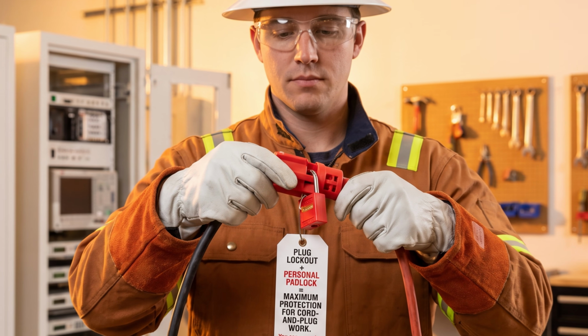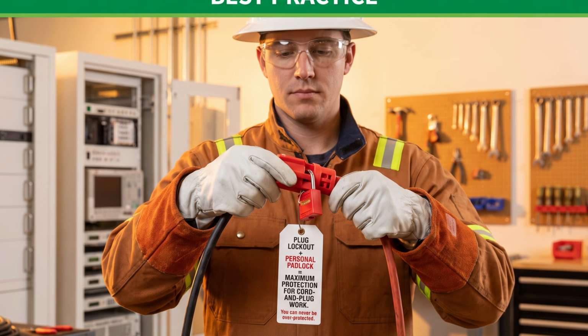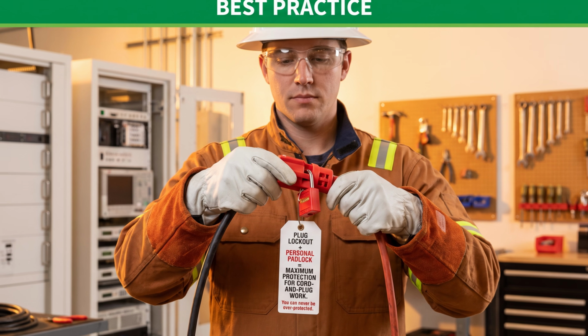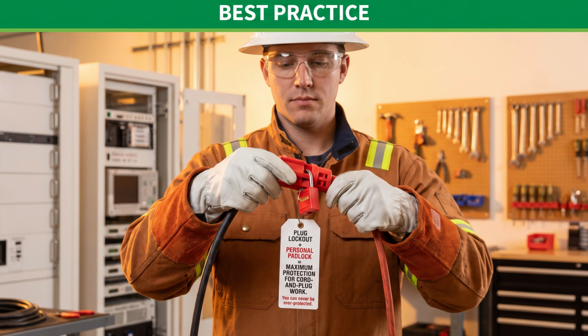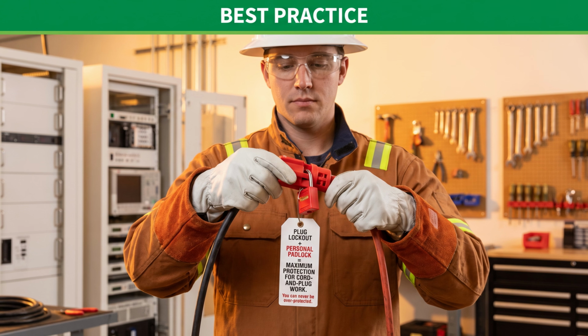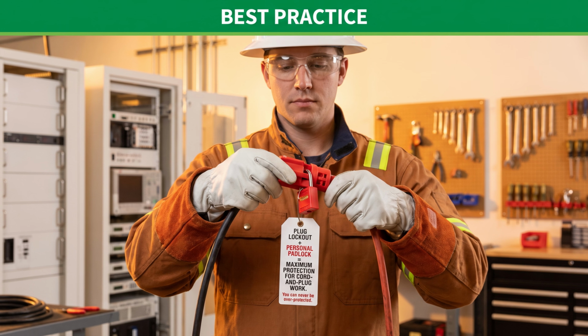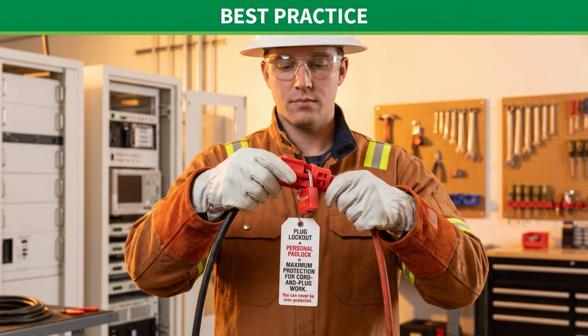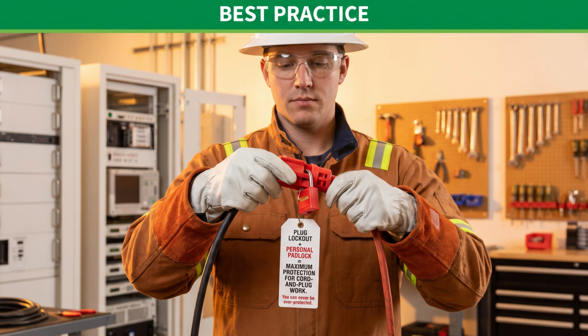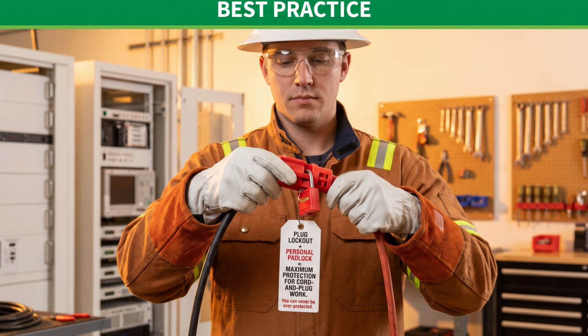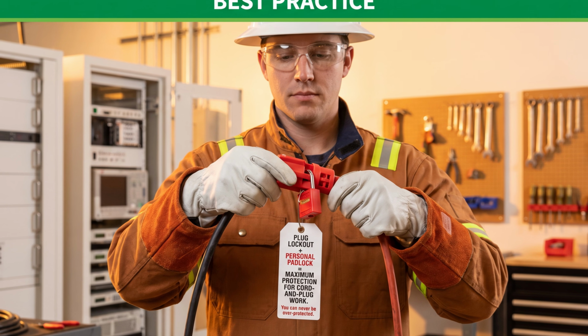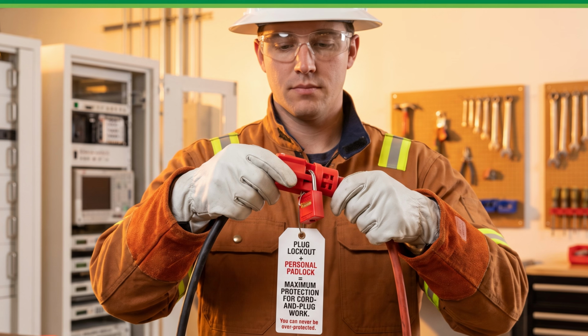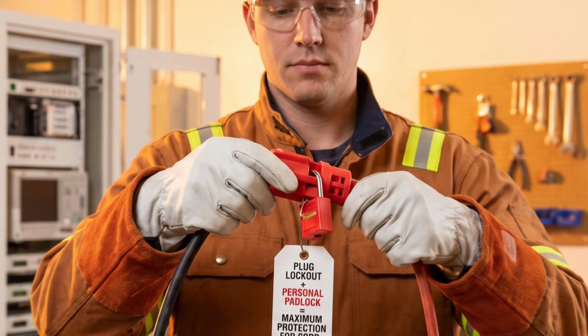For any cord and plug equipment where work takes more than a few minutes, both hands are needed, or the environment is shared, use a plug lockout device with your personal padlock. This gives you the flexibility of the cord and plug approach, while adding the physical security of a lockout device. You can never be overprotected. You can absolutely be underprotected. Build the habit of using a plug lockout. Make it automatic.